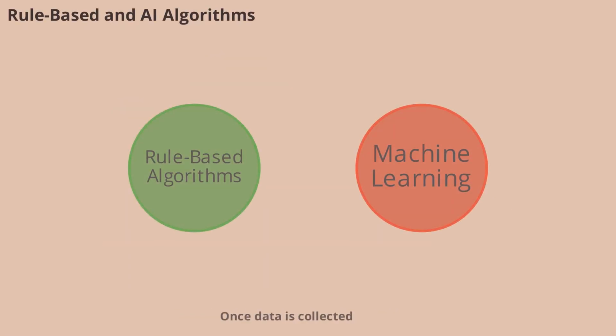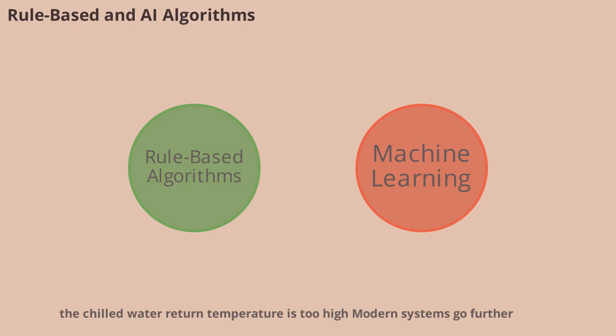Once data is collected, FDD uses rule-based algorithms or artificial intelligence to analyze it. Traditional systems rely on if-then rules, such as flagging a possible valve issue if the chilled water return temperature is too high. Modern systems go further, using machine learning models to detect complex patterns and predict faults before they occur.